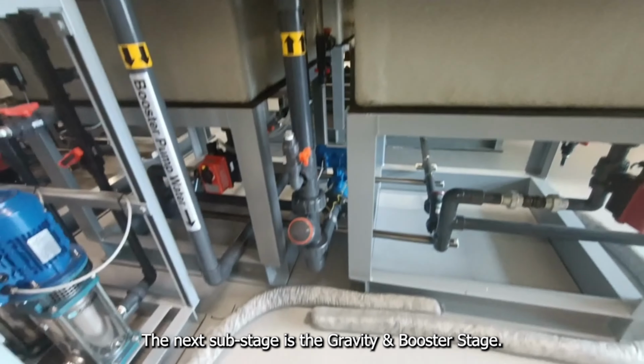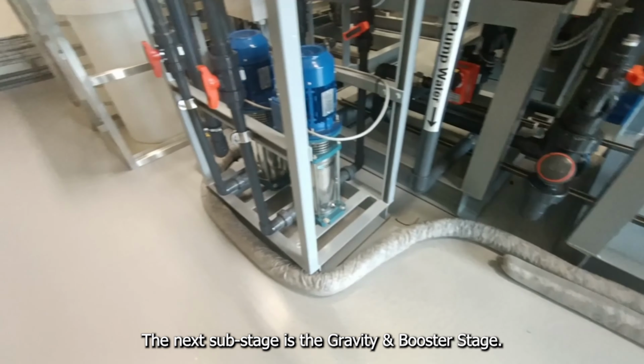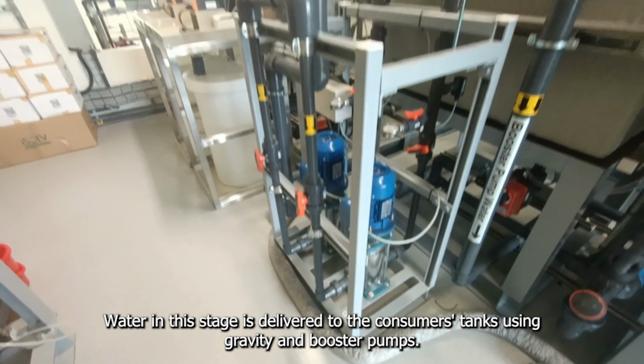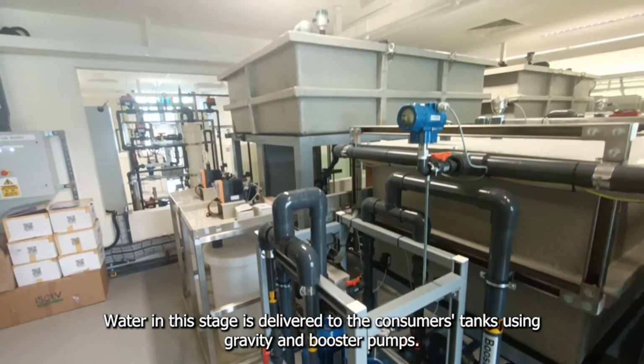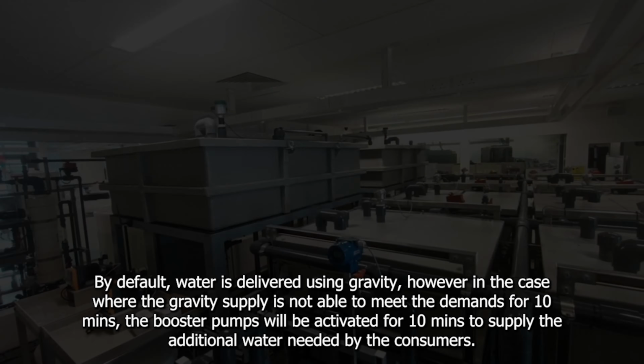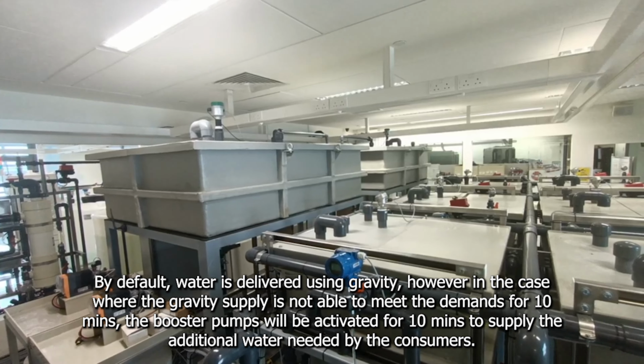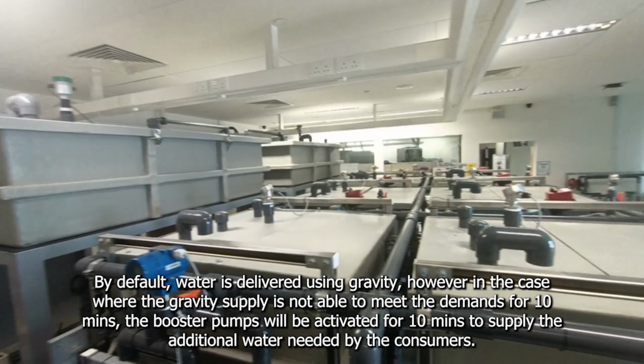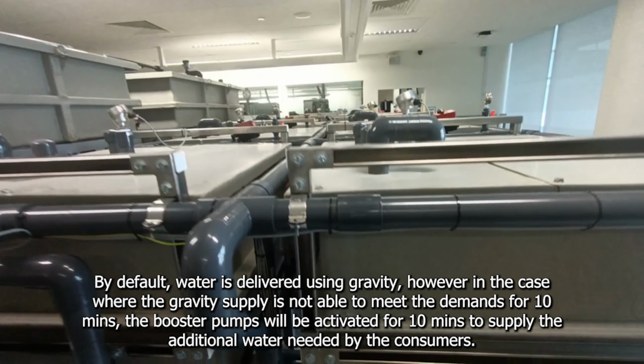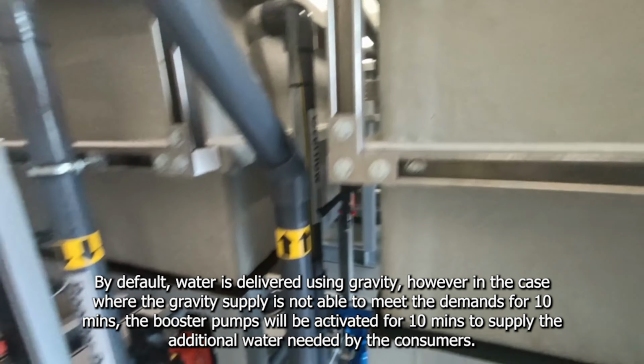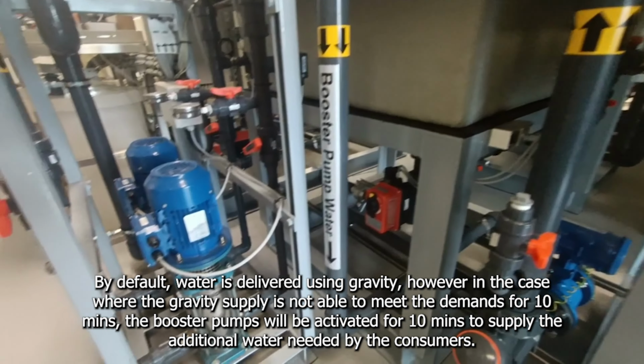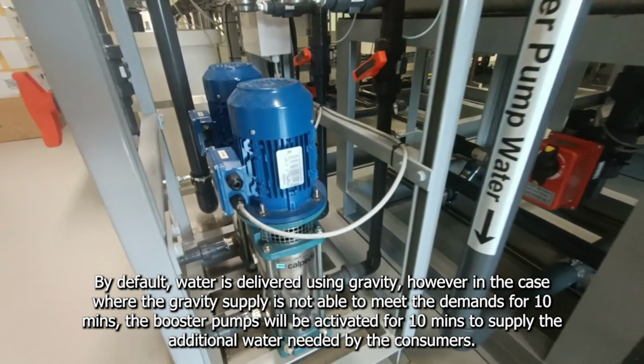The next substage is the gravity and booster stage. Water in this stage is delivered to the consumer's tanks using gravity and booster pumps. By default, water is delivered using gravity. However, in the case where gravity supply is not able to meet the demands for 10 minutes, the booster pumps will be activated for 10 minutes to supply the additional water needed by the consumers.